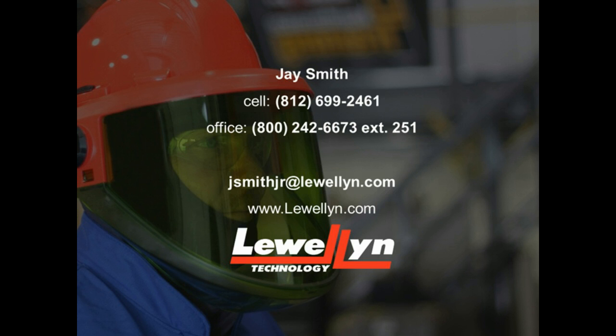Next one: how long is an arc flash study good for? Does the study expire? Well, the study itself doesn't necessarily expire. 70E has a regulatory comment in their standard that says no more than every 5 years you have to revisit your arc flash study, and it needs to be updated.